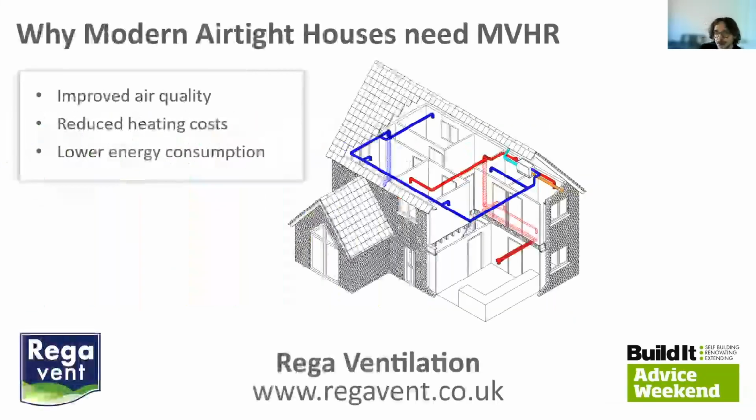So, to summarise, modern airtight homes need some means of ventilation in order to maintain a healthy environment, ensure a high level of air quality within a home, whilst preventing issues like condensation and mould growth. MVHR systems can offer around 90% heat recovery efficiency, meaning minimal heat is lost from extracted air.